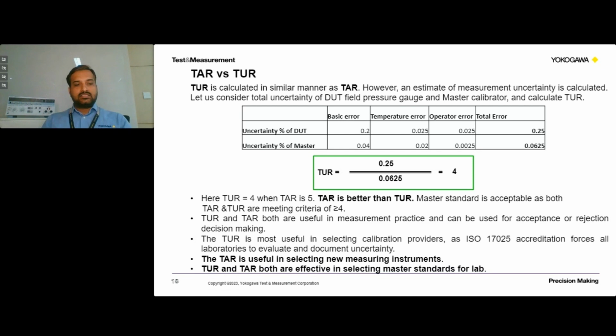And test uncertainty ratio and test accuracy ratio both are effective in selecting the master standards for lab. So when we go for a selection of the masters for lab or a master calibration instrument for lab, we need to check both test accuracy ratio as well as test uncertainty ratio.